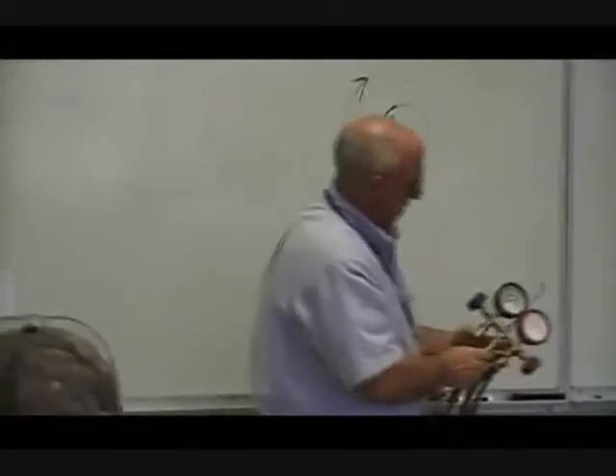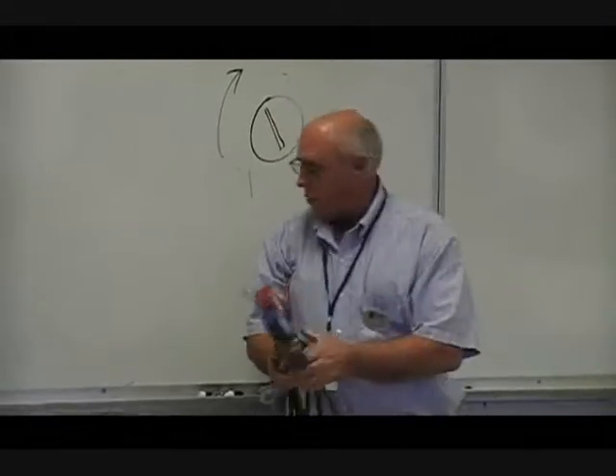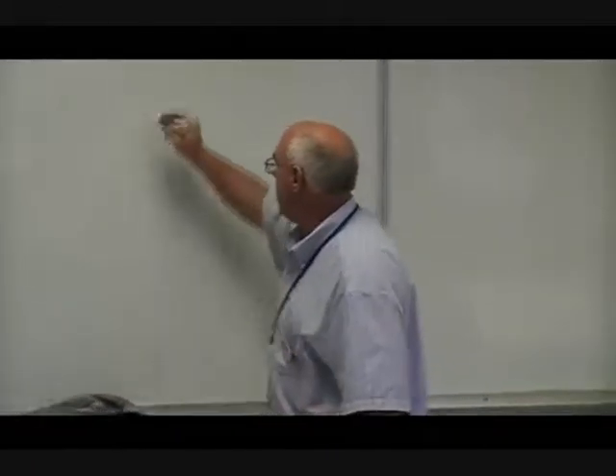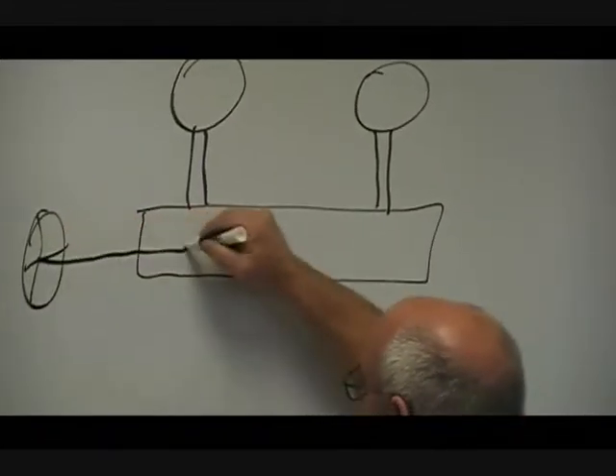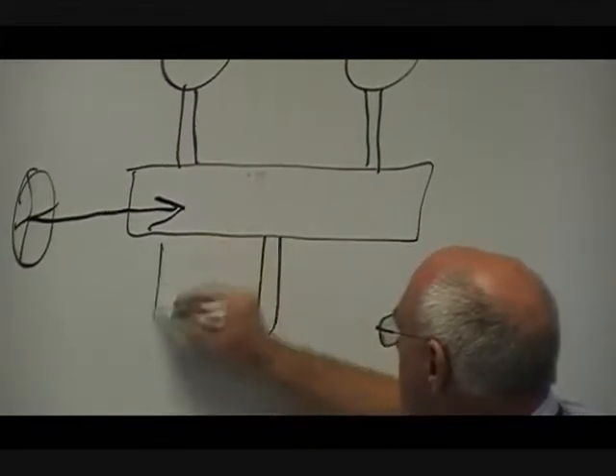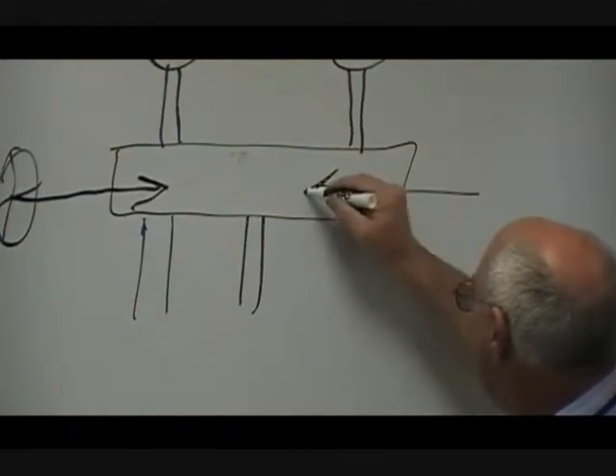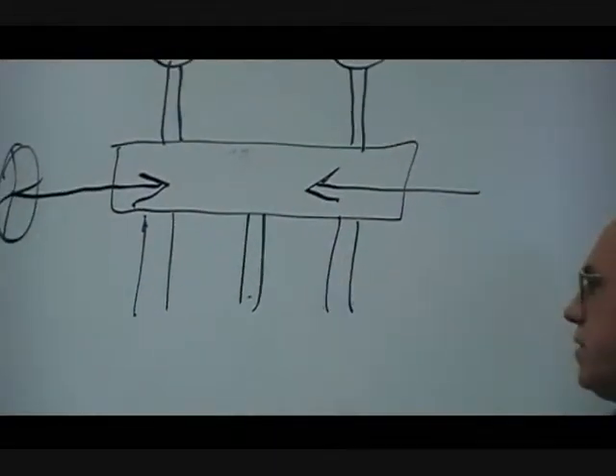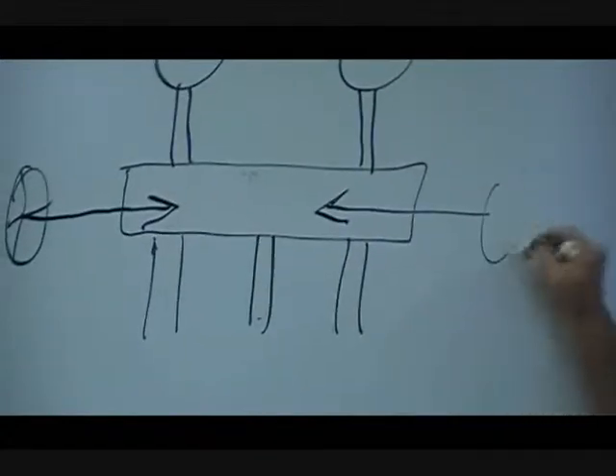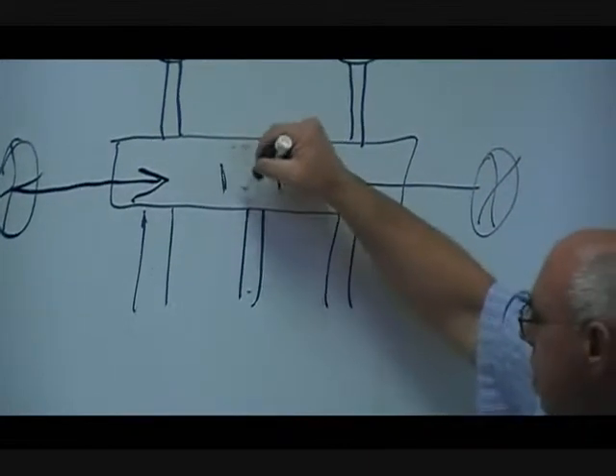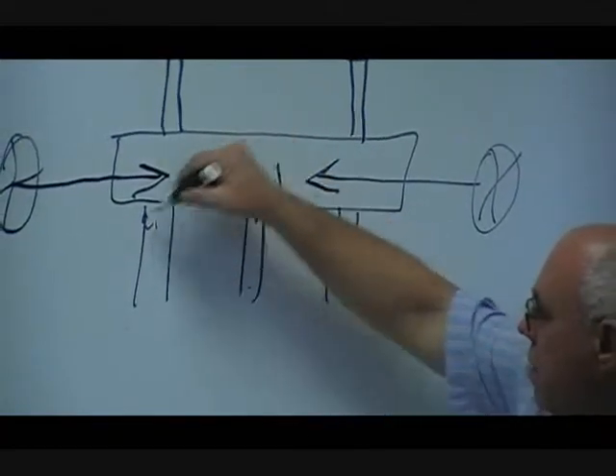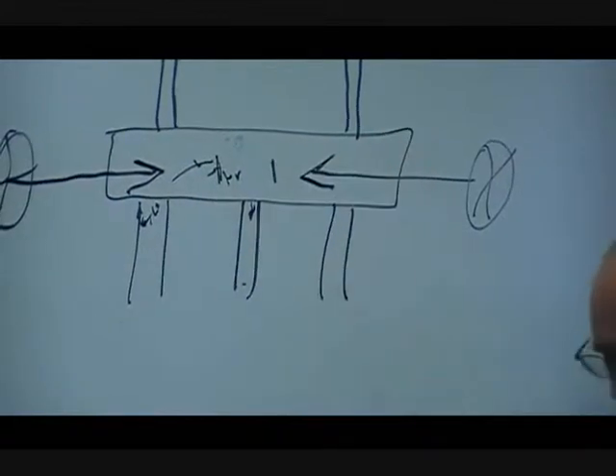I don't think I can emphasize enough about letting other folks use your tools. The way these gauges are made is if I were to draw a quick diagram of the manifold gauges, you have your gauge here, gauge here, port, port. We've got one port here, one port here, and port here. Okay. This center port, service port is sometimes called low pressure port, high pressure port. It does not matter how much you move this valve right here. It only stops the flow between the service port and the appropriate either low side or high side port, depending on which you're moving.